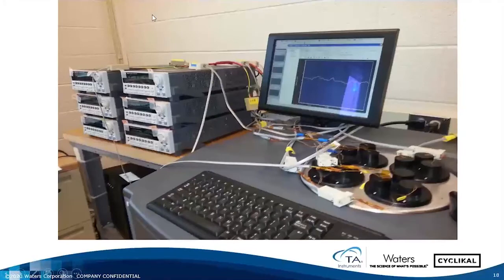This slide shows the equipment that we use. It's an older TAM3 equipped with 12 20 milliliter calorimeters with a fixed reference. We use Keithley 2602B current source meters for our electrochemistry, and this provides us with coulombic efficiency precision in the plus or minus 0.02 range.